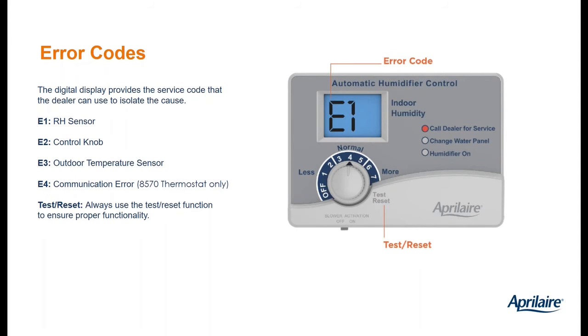E2, same idea. The internal diagnostics have said there's a problem with the control knob. So have the consumer turn the knob to test/reset. If the error code goes away, then we're fine. If it doesn't, then replace the humidistat.